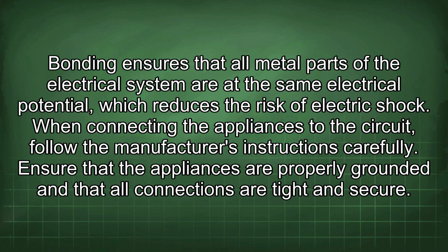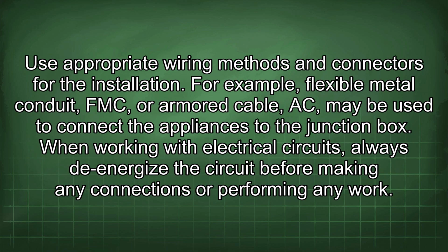of electric shock. When connecting the appliances to the circuit, follow the manufacturer's instructions carefully. Ensure that the appliances are properly grounded and that all connections are tight and secure. Use appropriate wiring methods and connectors for the installation. For example, flexible metal conduit (FMC) or armored cable (AC) may be used to connect the appliances to the junction box. When working with electrical circuits, always de-energize the circuit before making any connections or performing any work.